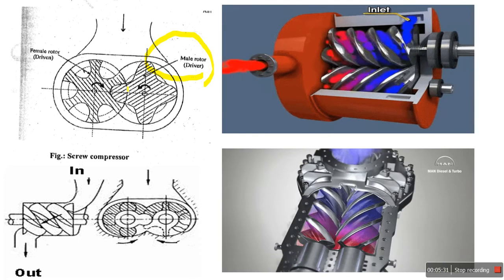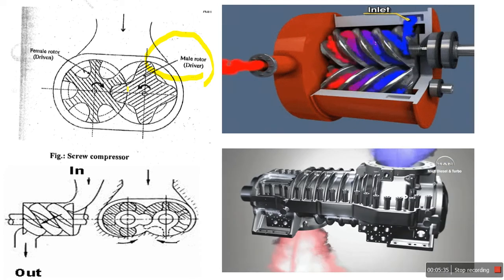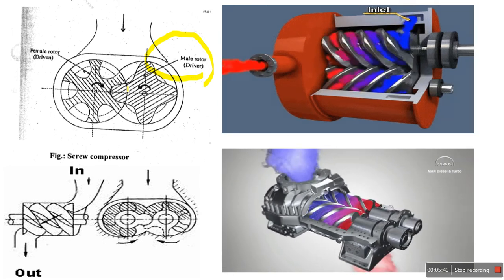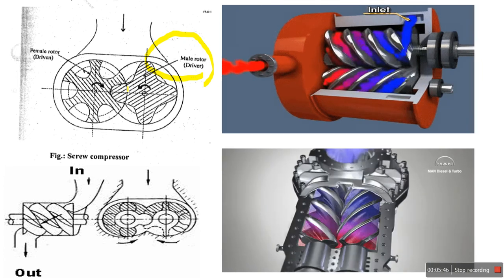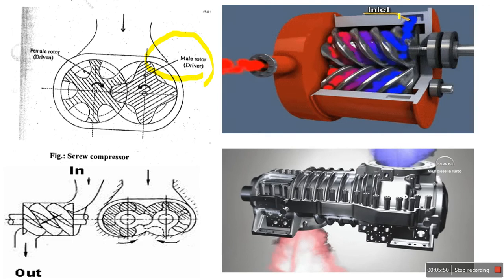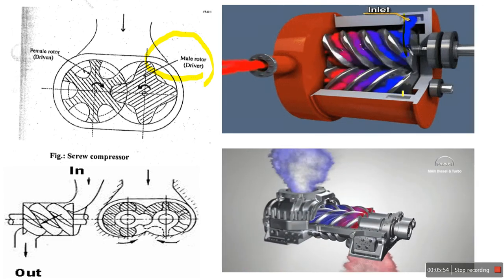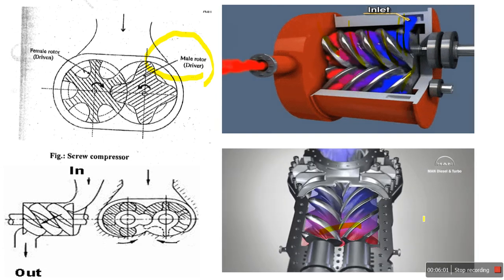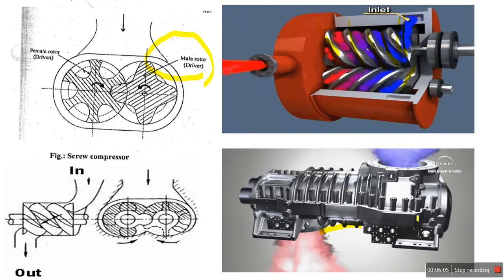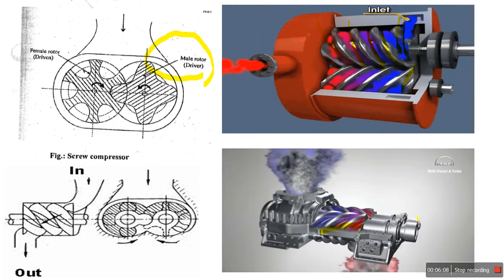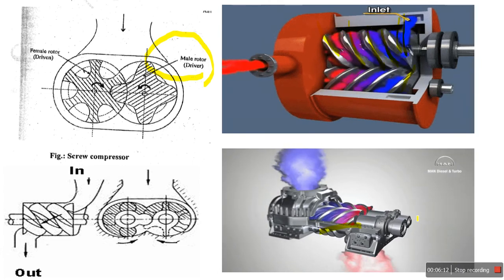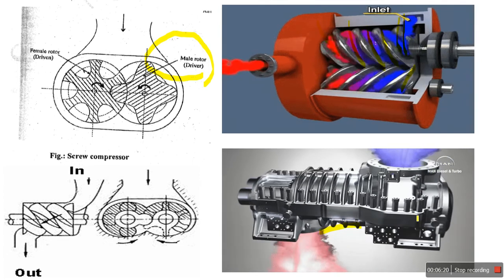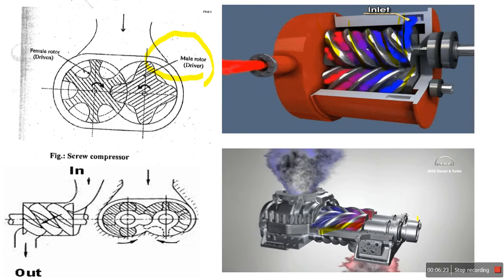During compression, further rotation causes the meshing of another male lobe with the female interlobe space on the suction end, progressively compressing the air in the direction of the discharge. The inlet air enters the chamber and starts to squeeze — that is the key principle of the screw compressor: squeezing of air progressively and continuously. At the discharge point, the discharge port is uncovered and the compressed air is discharged by further meshing of the lobe and interlobe space.